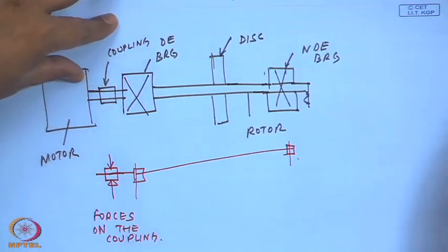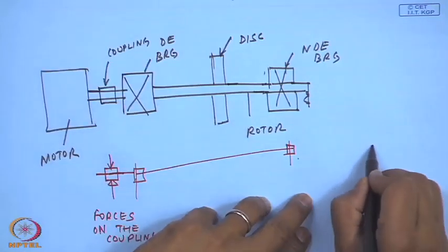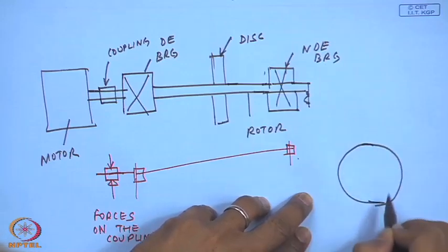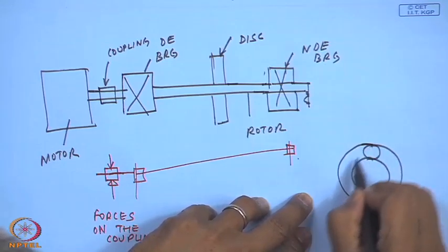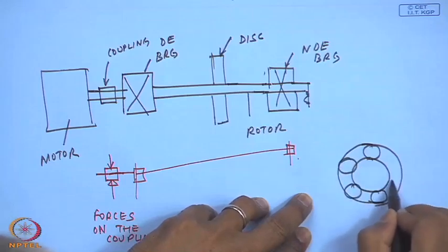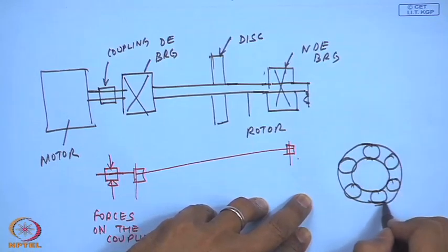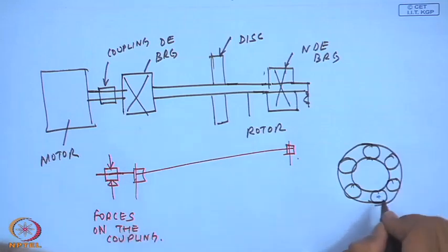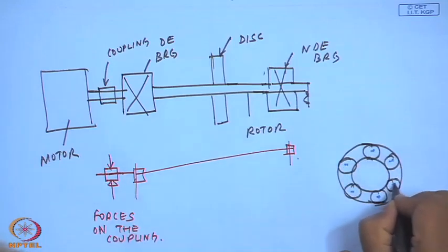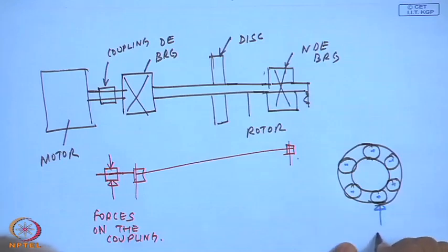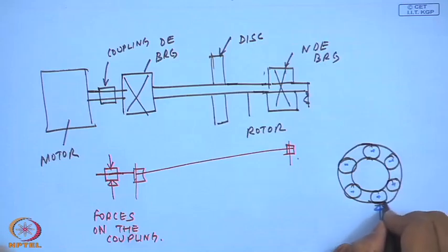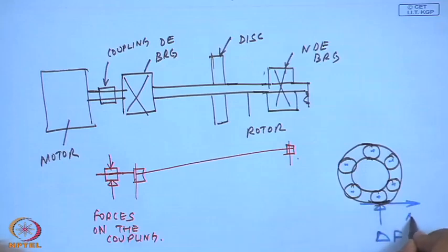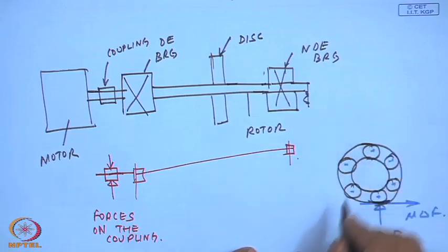Then what happens? Because of the forces on the couplings, this affects the bearings. If you think of a bearing, these are the rolling elements, and there are certain clearances between them, and they are allowed to move. So there will be some sort of extra force, which I am writing as delta force, and because of this force, there will be increase in the friction. The friction force will increase, and this is going to be the source of heat generation.